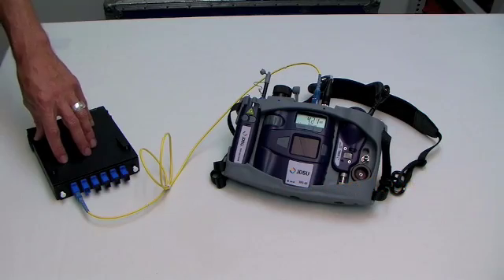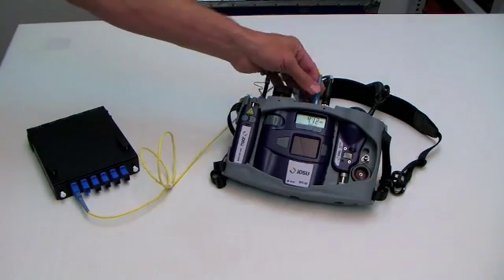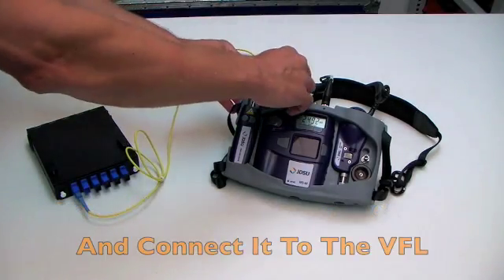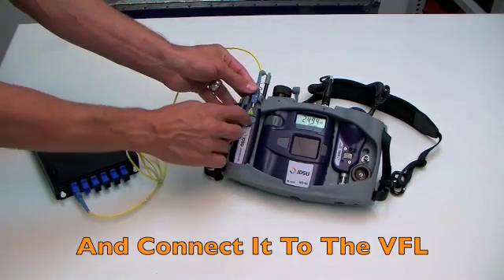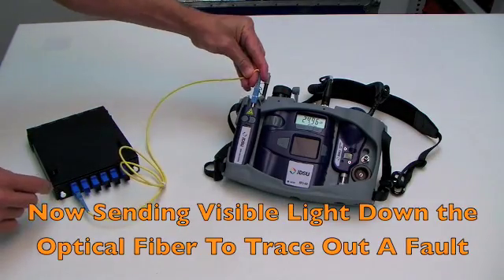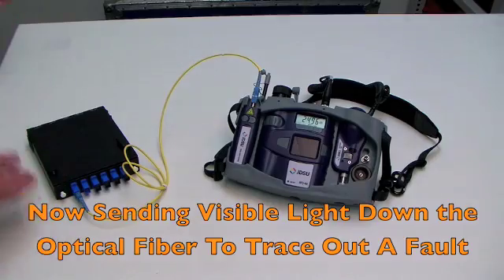Or he's troubleshooting a problem on this line and he doesn't have power, he can take the test lead out of the optical power meter and put it right into the VFL. Turn the VFL on, and now he's sending visible light down the optical fiber so he can trace out a fault.